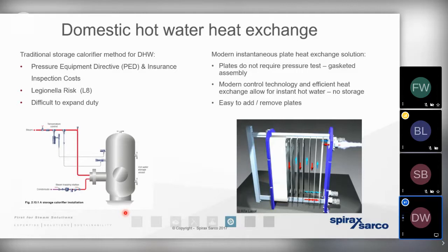But we also know that that buffer vessel is going to be a fixed size. And the little shell and tube heat bundle assembly at this point here is also going to be a fixed size. So that's what we refer to as having a fixed A value, a fixed heat transfer surface area value that we looked at on those previous equations. So it's very easy, and indeed very tempting, for any manufacturer to oversize a heat exchanger. They think they're doing the right thing by ensuring that the client has a constant supply of hot water readily available, but that can bring a number of different problems.